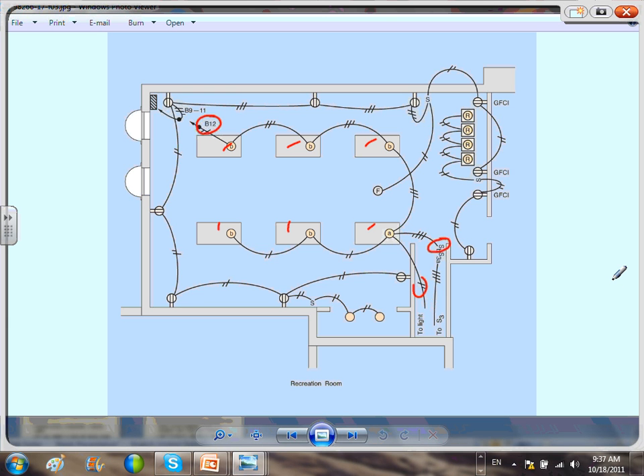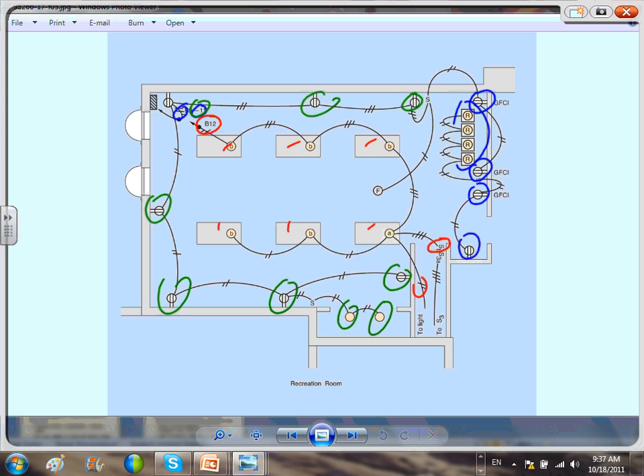The second circuit, they brought 2 circuits, guys. They brought 9 and 11, multi-wire branch circuit. And if I understand right, I think they brought one of these circuits to feed this receptacle, this receptacle, this receptacle, this receptacle, as well as all the lights. Okay? And the second circuit, one of them is feeding these receptacles on this wall plus these lights. So they have 3 circuits coming to this area. One of them is a multi-wire branch circuit. They took a hot and a neutral, fed all this area.